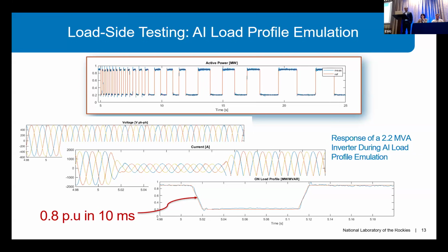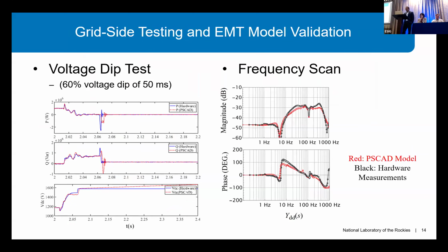If we want to go faster, we need to, of course, tune our grid simulator, but that might result in some control interaction. So I'm trying to say that it requires additional tuning, but it's still possible. But in any case, this ramp rate of going from 0 to full power within 4 or 5 milliseconds is much more than what you need for data centers. And that makes us basically a good place to test data center power supply equipment.